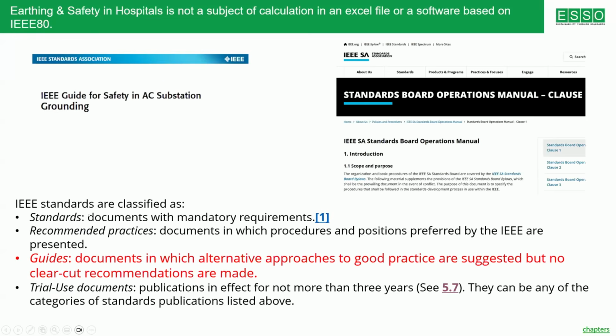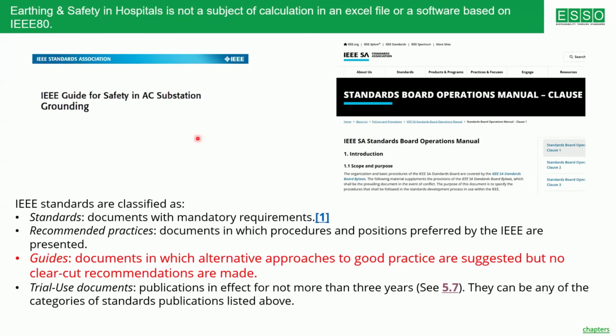Why I'm returning back to the same slide again is this is becoming a big challenge, because we are trying to educate the market that look, IEEE 80 is applicable for a substation, not for a hospital, not for the low voltage electrical installation. But still, every day, 2-3 phone calls I used to get, and they wanted me to help with an Excel sheet how to make everything calculation as per IEEE 80. So please note, this is not for a hospital installation. Fault current of 50-65 kiloampere, earth fault current of such large magnitude are very, very rare.